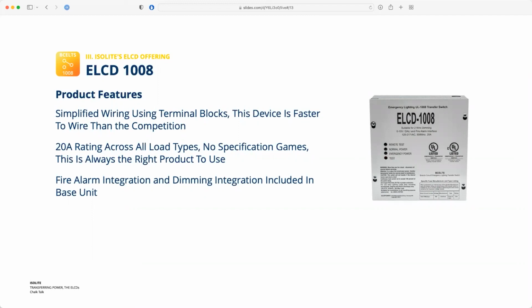So what we've done is we've built an all-in-one box that has terminals, so you don't have to do flying leads. You don't have to mount these external fuses. All the fuses are built into it so that it's always safe and easier to wire. It's a surface mount device. You can bring pipes straight to it instead of cranking it into a 4x4 junction box. So it's easier to install, and it's always going to be installed safely.